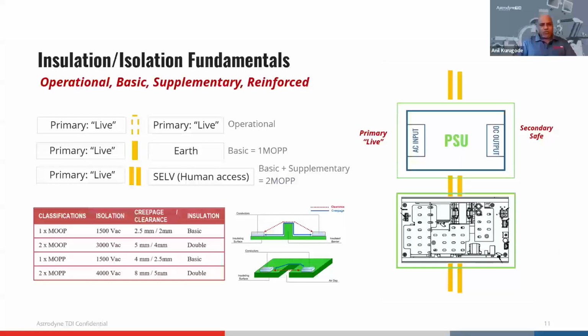So the most important requirement is: whenever you have a live circuit from primary to primary, you don't have to worry so much - it's just an operational requirement and human contact is never there, only intended to make sure one circuit works along with another. Whenever earth is involved, you have a primary circuit and an earth circuit - the circuitry is connected to earth or sheet metal - then all we need is one level of insulation, called one MOPP, meaning Means of Patient Protection. That's enough to say it's insulated.